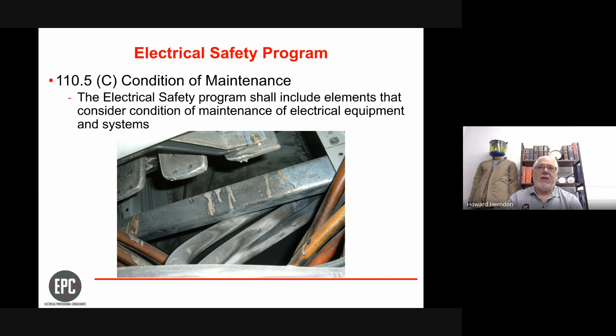Like many of our other pieces of equipment in our industries, the equipment, whether it's a valve or a circuit breaker, has to be exercised to the point that it can properly operate. Grease has to be moved around so that those hinge points can operate properly and the overcurrent device can operate. And when they don't, you have circumstances where you try to move the handle from on to off, and it won't move. Or the handle moves, but the mechanism inside doesn't. Or we turn the overcurrent device off or circuit breaker off, and then it won't go back on. So the condition of maintenance is a huge consideration in our electrical safety program.